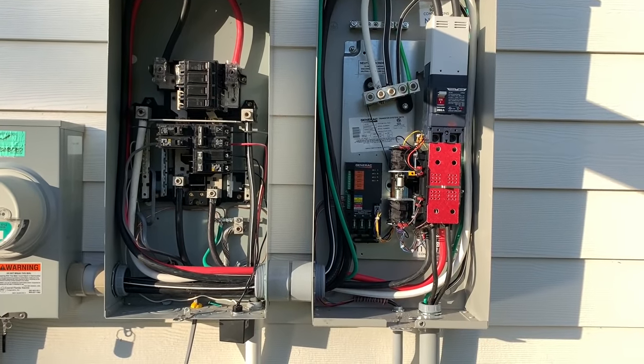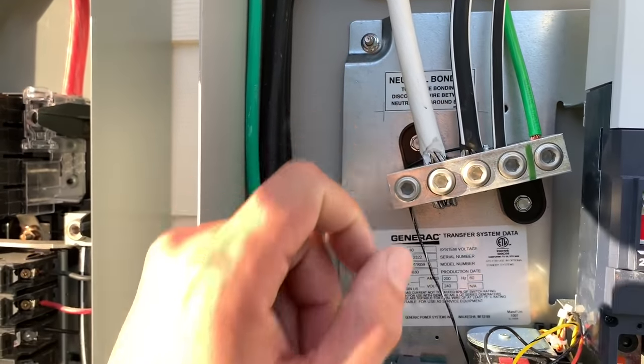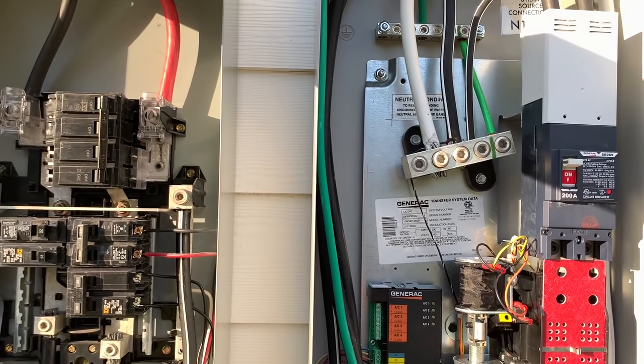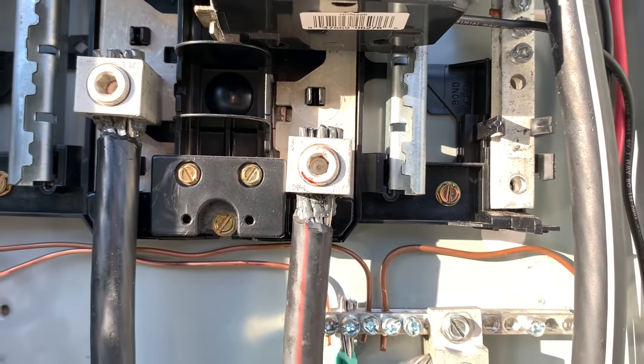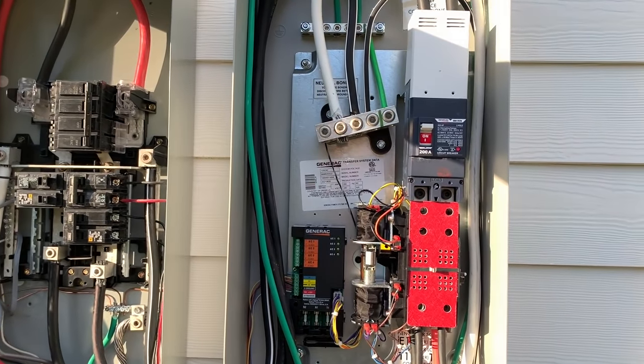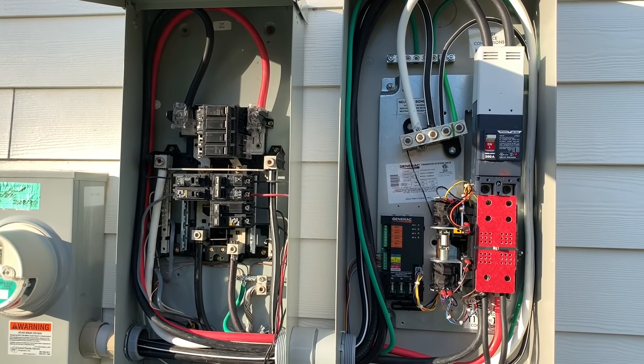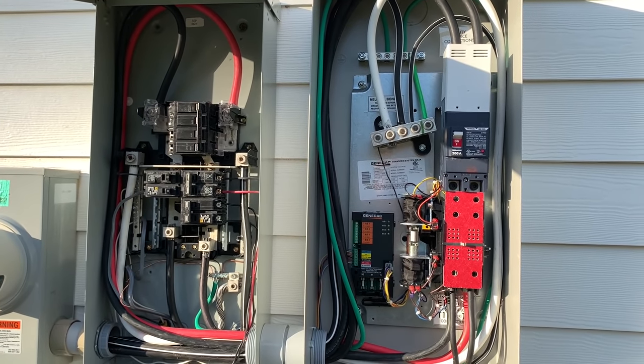With that being said, let's jump into some of the questions. I got a lot of questions about not putting No-Ox on my terminations. Most of the time in years past, you were required to use an antioxidant compound — that little gray goop you can see on the wires. However, it's actually no longer required by the National Electrical Code. The aluminum wire these days is actually an aluminum alloy, and they still sell the compound, and some municipalities still require it.